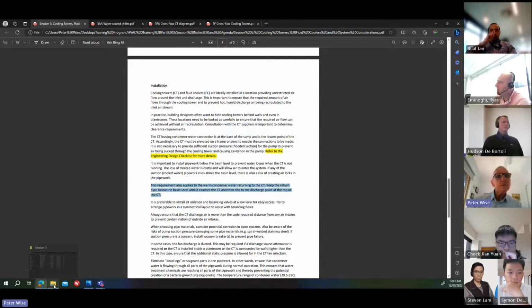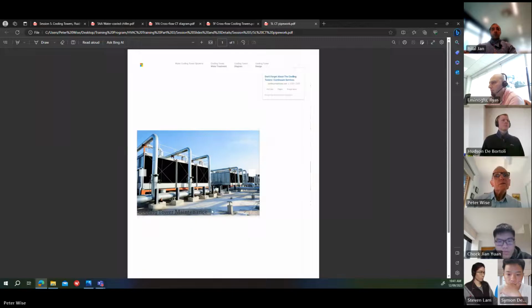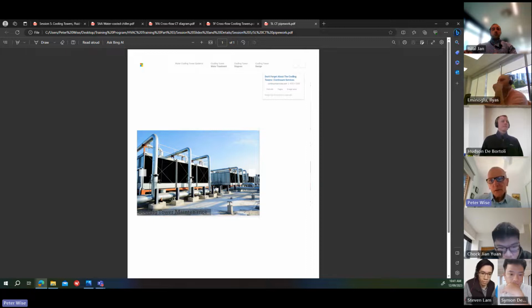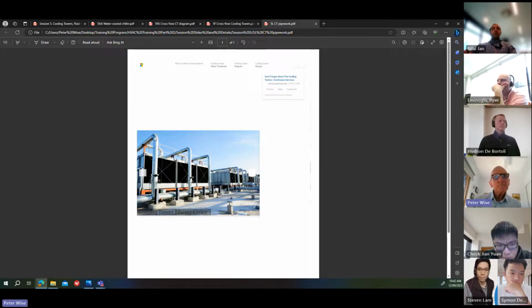I'll just show you a diagram of that. So this one here shows the return water, the warm water coming back. You can see that they're running the pipe below the water basin level of the cooling tower, and then it rises up to the top of the tower. Now, obviously there'll be a head of water above the basin when the cooling tower turns off, and there is a risk that some of that water will be lost.